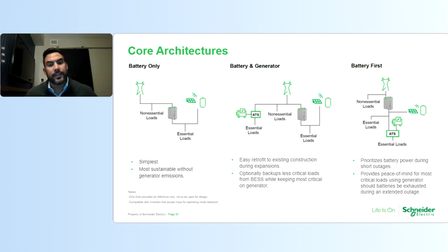So these are some of the core architecture. In most single line diagrams, I would say most of them, the battery only scenario will have a photovoltaic system, and the client will add some type of energy storage system there to help reduce peak, to help perform peak shaving, take advantage of time of use management. And most facilities will have PV and or energy storage system. There's some opportunities here. If you scroll to the middle here, you'll have battery and generator. Or perhaps maybe it's an existing facility. They had a generator there that was providing power to legally required loads, and this facility now wanted to add a photovoltaic and energy storage system to tap into the energy economics of the microgrid, right?